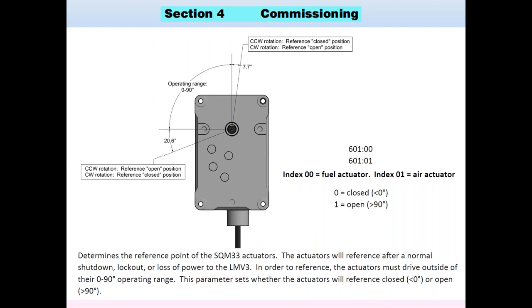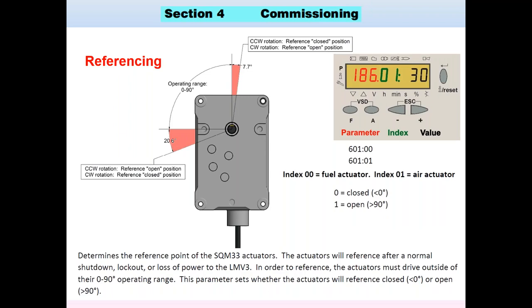All actuators on the LMV3 must have referencing — a range of operation outside the 90-degree operational window, going below 9 o'clock or above noon. In clockwise rotation, the 1 o'clock setting is the reference open. In counterclockwise rotation, the reference open is at the 8 o'clock range. These have indexes — parameter 601 — where the index chooses air or gas, and the value chooses either open or closed for referencing.